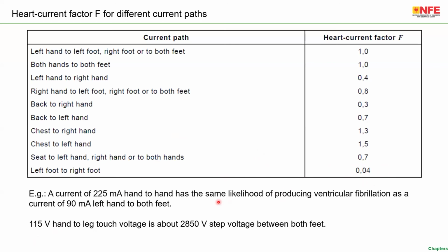Now, from these two tables, the touch voltages are calculated in the standard and the limits are set in the standard. For example, for 1 second disconnection, 115 volt is the hand to leg touch voltage. If we calculate the same potential for step potential, it comes to about 2850. You multiply it by, you have to calculate as 0.04 is the heart factor. So basically, in a typical situation, if we say 115 volt is the touch voltage, in the same condition the step voltage can be 2850. These figures or these parameters can be calculated from the heart factor.